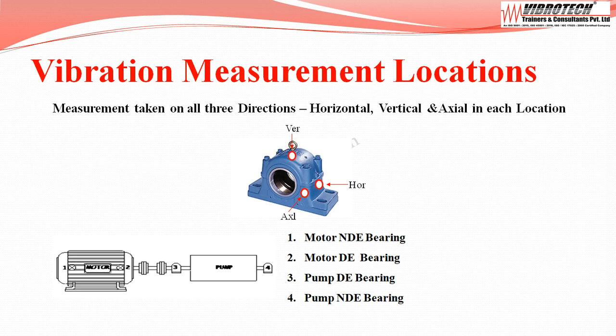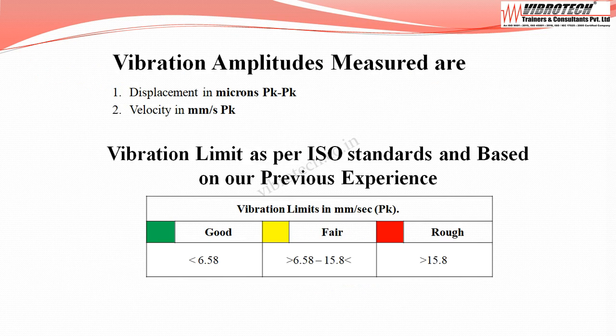Vibration measurements are taken in all three directions: horizontal, vertical, and axial. Measurement locations are motor non-drive end bearing, motor drive end bearing, pump drive end bearing, and pump non-drive end bearing. Vibration data are collected in terms of displacement in microns peak to peak and velocity in millimeters per second peak.